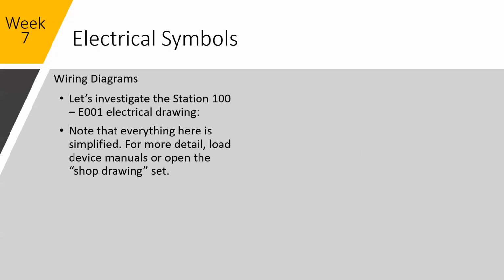When you look at these electrical drawings, even when you get professional electrical drawings like this, say you're wiring up a transformer or a level transmitter, you always have to go and find that piece of equipment's manual. That manual is going to have a detailed wiring diagram that tells you what terminals are for the high voltage, for the low voltage, for the fault, and how to wire it up for different power configurations and different voltages, especially if you go into a country that has 240 instead of 120, or 50 hertz instead of 60 hertz. These are things you just have to pay attention to, and they're going to be different for every single device.